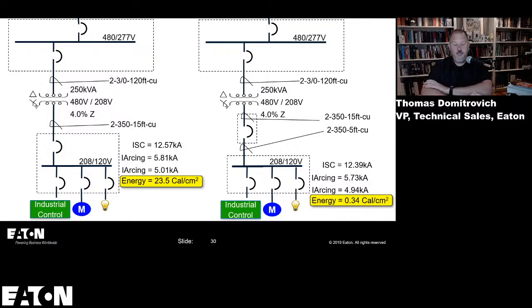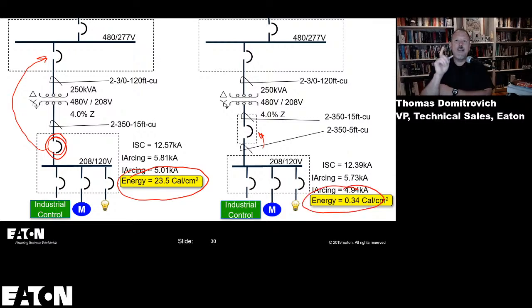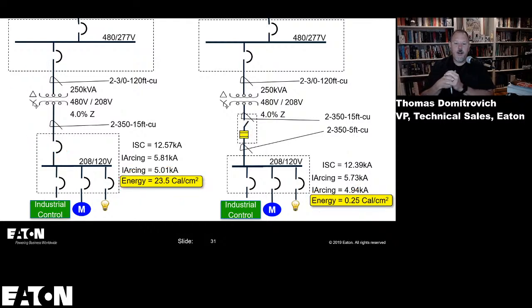Here's an example of a 250 kVA transformer. Because this breaker is integrated with this panel board on the secondary of that transformer, I'm relying on this upstream circuit breaker feeding this transformer, and my incident energy is 23.5 calories per centimeter squared. That's a big boom, all right? To knock that down, simply moving the breaker into its own enclosure, or putting a fusible switch in there, whichever you desire, I reduce the incident energy to less than 1 calorie. And that is daily wear. That is huge. If I put a fusible switch in there, I could take it down to 1/4 of a calorie per centimeter squared.